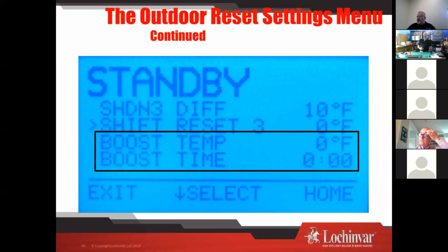Well, boost temp, boost time allows you to say, all right, if my boiler has a sustained call, and let's just say we program in here in this boost time 20 minutes, it will automatically boost the temperature by whatever you tell it right here. So maybe say, hey, you got a sustained call for 20 minutes, bring it up 15 degrees. If it goes another 20 minutes, bring it up 15 degrees. And it'll automatically boost that temperature up for you. So you can be a little more aggressive in your outdoor reset.